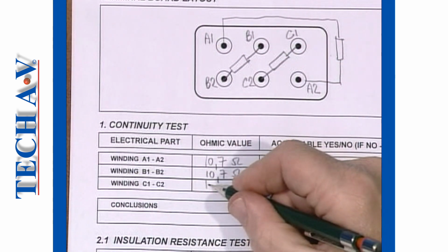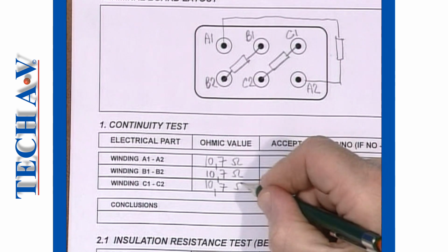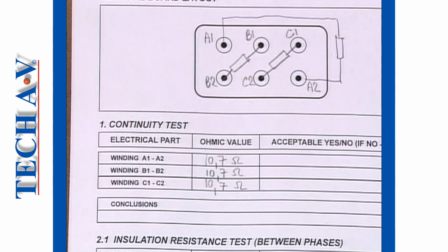The resistance values should all be of a similar value. Readings within a 5% tolerance band indicate that the windings are balanced. A tolerance greater than 5% requires further investigation as to the cause of the imbalance.